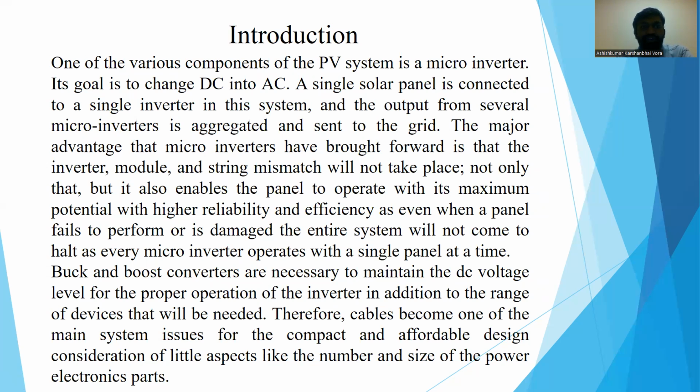The major advantage that microinverters have brought forward is that inverter module and string mismatch will not take place. Not only that, but it also enables the panel to operate at maximum potential with higher reliability and efficiency. Even when a panel fails, underperforms, or is damaged, the entire system will not come to a halt, as every microinverter operates with a single panel at a time.